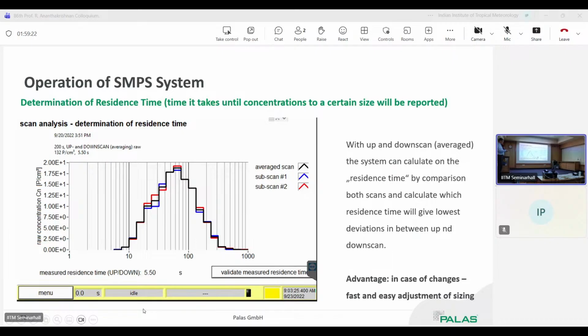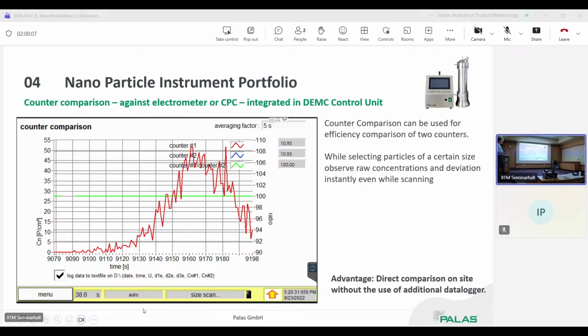And what we also do is residence time, which is often a very important topic. You need to know from the column to the particle counter how long it takes until the signal appears. This we can determine by a function which we integrated. So we do both down scan and up scan and average scan, and the residence time will then be determined by the system, and this you then set after validation into your system. It will not be set automatically because sometimes scans are not so good, so you set it finally. And we do counter comparison.